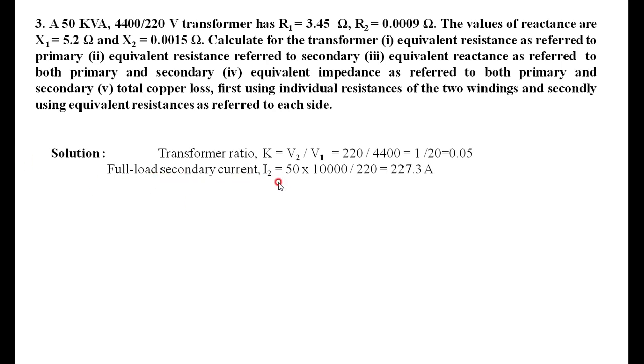The full-load secondary current is calculated as kVA rating divided by secondary voltage, that is 50,000 divided by 220, giving 227.3 amperes. The primary current I1 is then found using I1 equals k times I2, giving 0.05 times 227.3 equals 11.36 amperes.